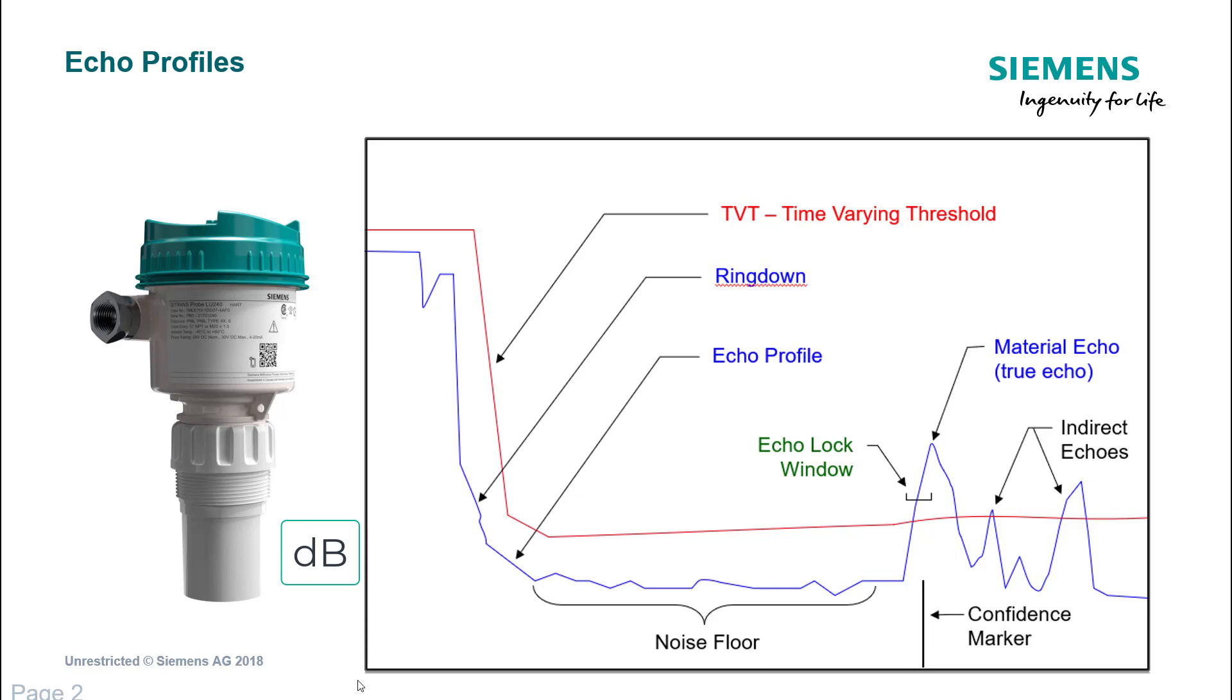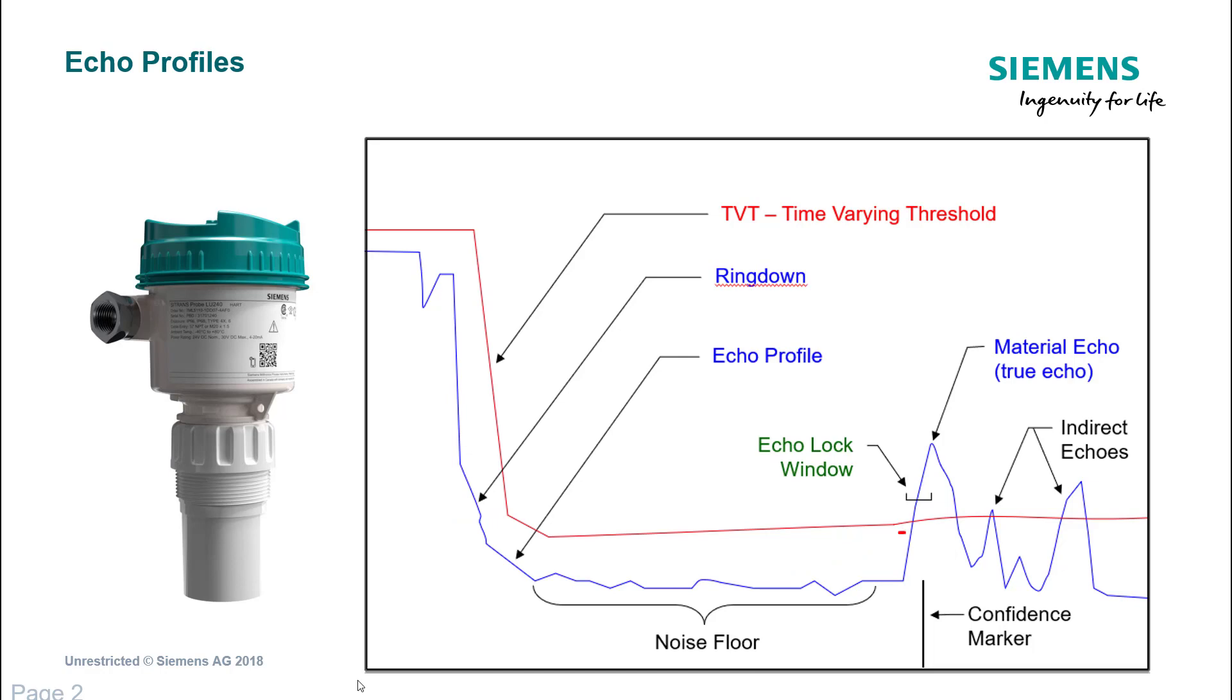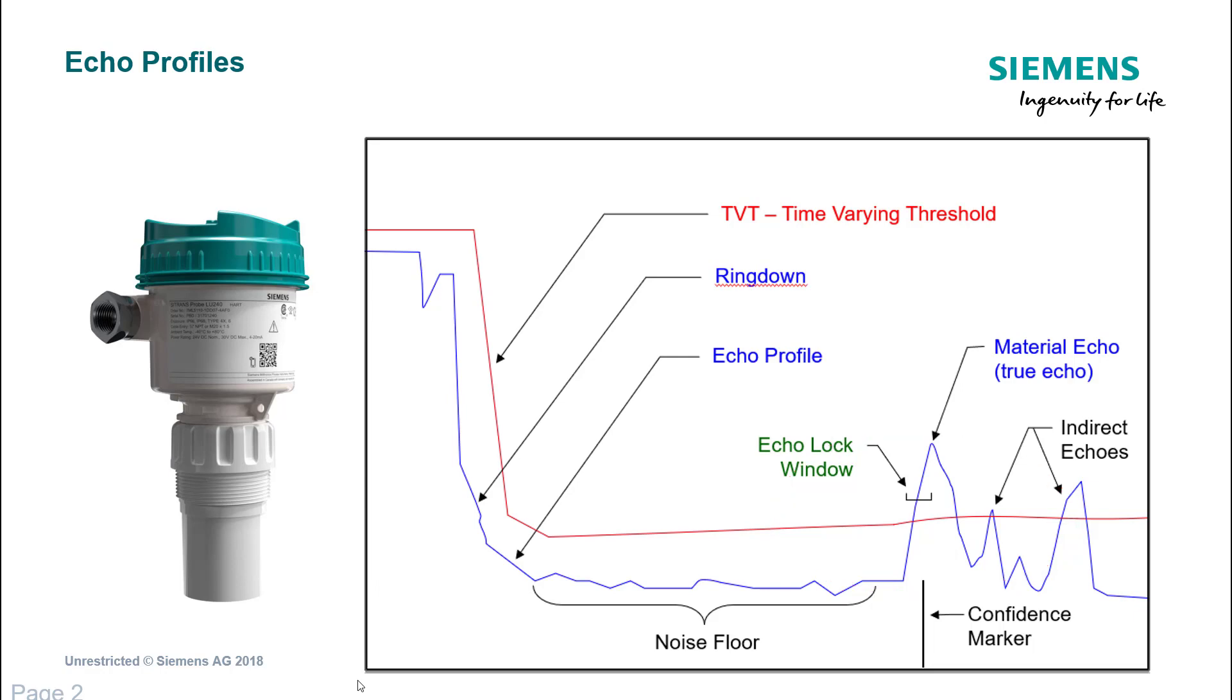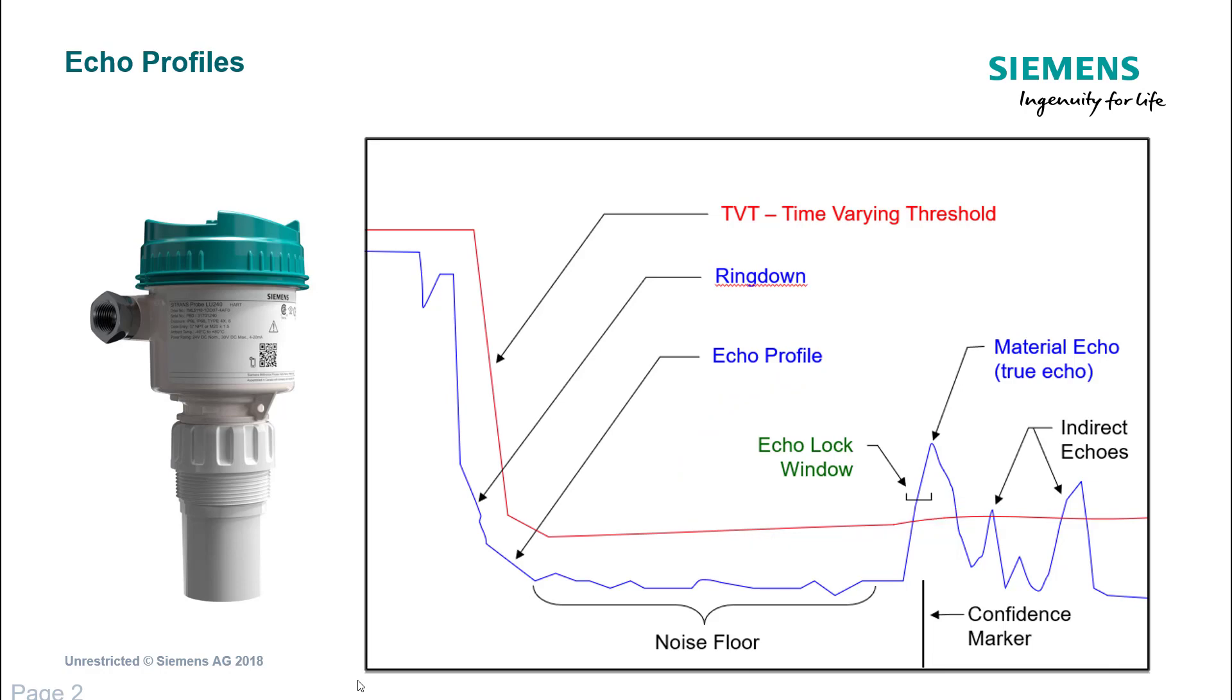It's easy to understand with sound. The signal travels through the air, this clicking sound that you can hear from an ultrasonics transducer. It hits an object, either liquids or solids, reflects that back off like an echo, and then it comes back to the transducer. We then get a signal going vertically, not perfectly straight going up. Depending on the technology it will be narrower. Once we've locked onto that, there's some sort of window. Siemens calls that the echo lock window.